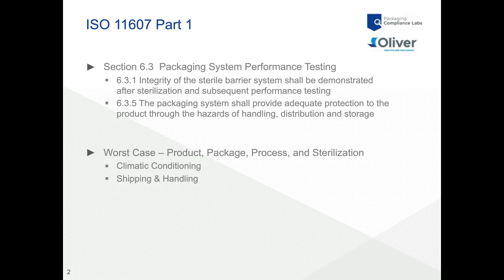The guidance document is also going to tell us to look at worst case scenarios. So when we go through some of the case studies we're going to run through, we're looking at worst case scenarios with respect to worst case sterilization modes and cycles, worst case product, medical device, and the worst case package configuration and process parameters. So we're going to be running at our worst case or limits within the processing of our packaging components, high and upper and low limits. And then climatic conditioning is going to be a part of that as well, and then the shipping and handling aspects as well. And Ryan will walk us through that.